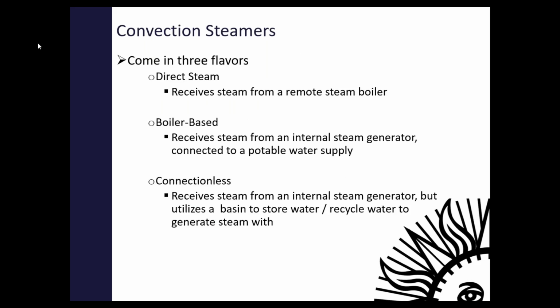Convection steamers come in 3 flavors. So one convection steamer will receive steam from a remote boiler. These are probably the worst, the most lossy, I should say, because running this piece of equipment, you need this piece of equipment all year. You can't just shut down your steam boiler that's also serving your hot water, your space heating. You can't shut down that boiler just because you have this convection steamer on it.